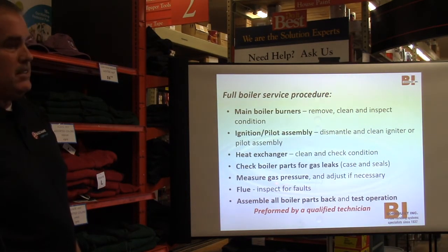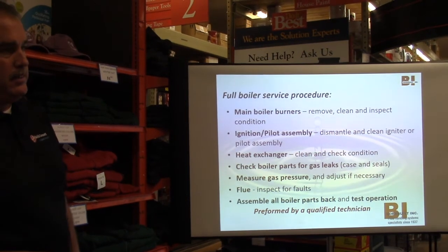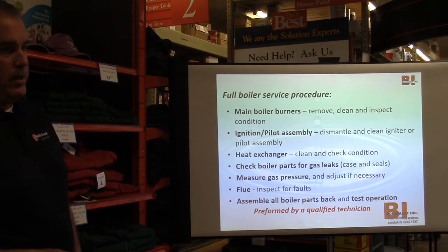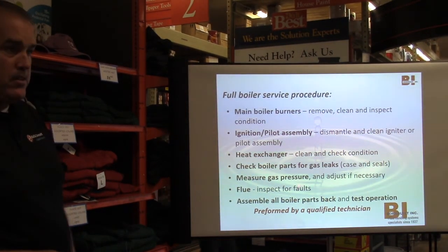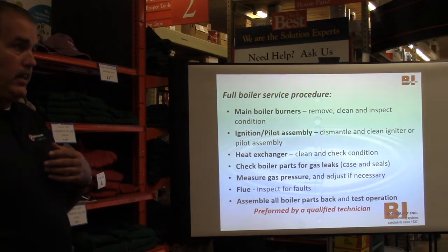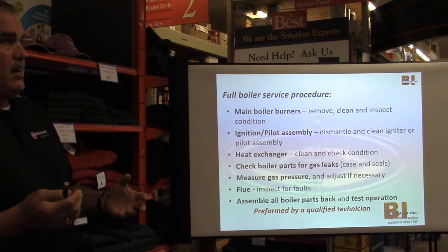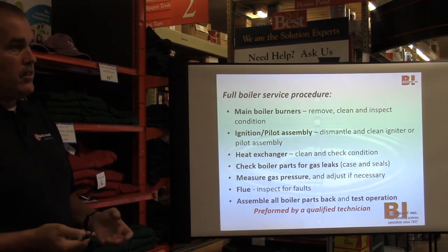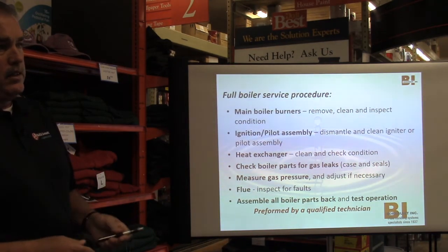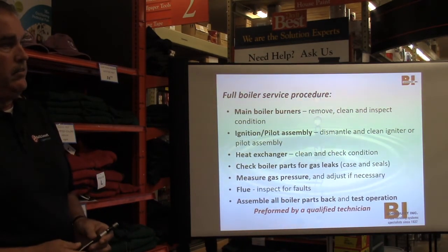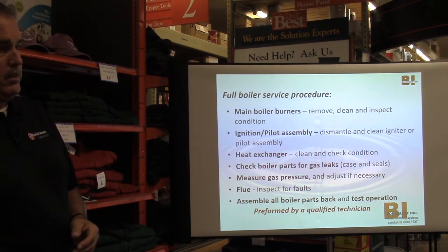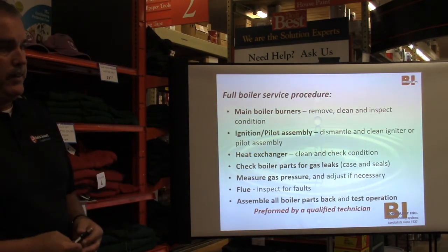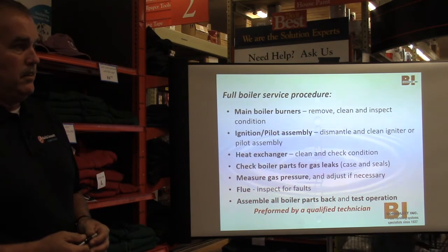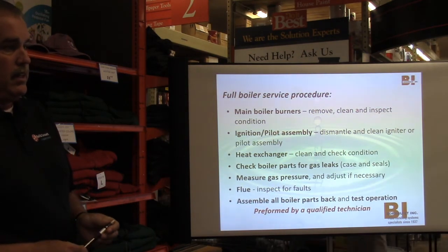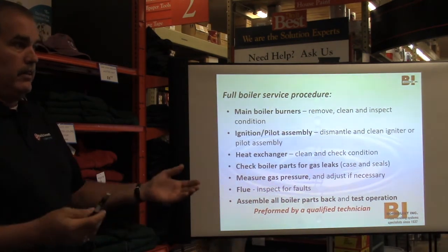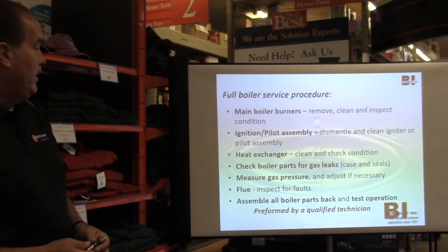They can also have means of measuring. They have what's called a manometer, which can measure real low pressure, like gas pressure. So they make sure that you've got sufficient gas. Because in Chicago, I don't know so much around this area, there are areas where the utility will only promise 4 or 5 inches of gas. That's why these big buildings downtown have gas boosters to run their systems during peak time, when everyone needs the gas.